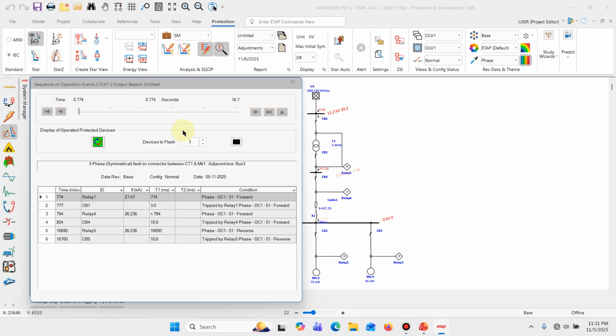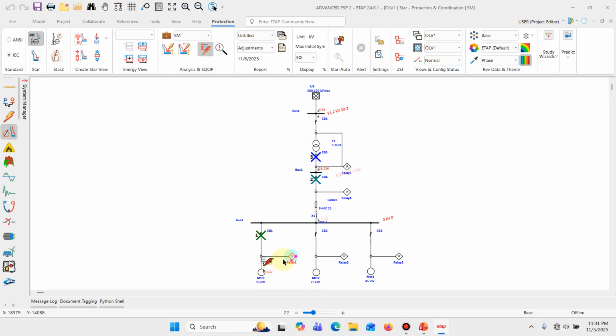And we can see the sequence of operation: relay 1 CB1, relay 4 CB4, relay 5 CB5. They are all tripped by overcurrent 51, so time overcurrent protection. So we can see the sequence 1, 2, 3 over here. So in this case, can we say that the protection coordination is accurate? The selectivity is there. Okay, let's see if the fault is on this section.